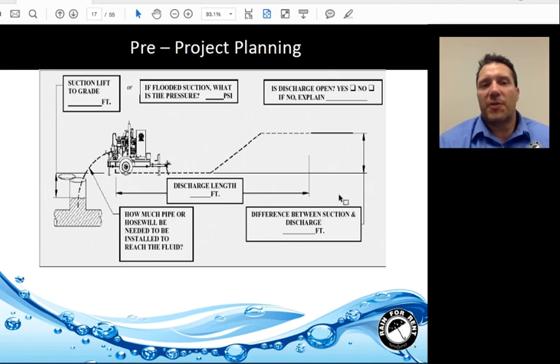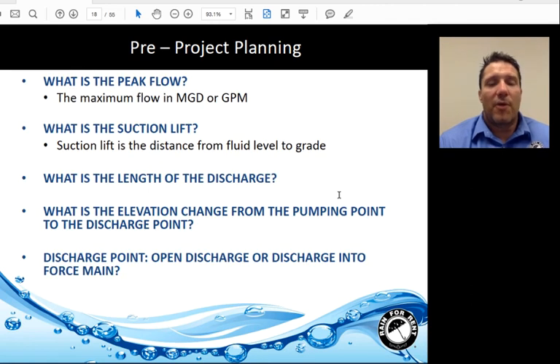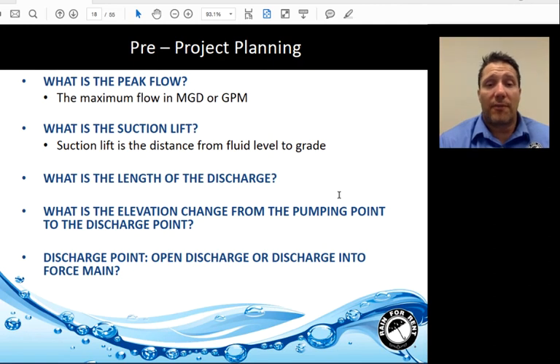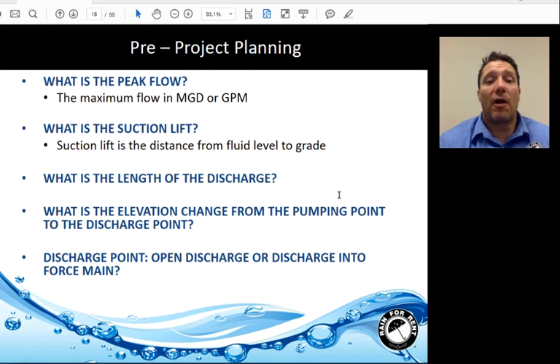This diagram is a good place to record information about the project site. The most important item is peak flow, followed by suction lift and fluid level to grade. The other items — length of discharge, elevation distance between pumping point and discharge point, and what needs to happen at the discharge point — are all items that, once known, will be used to design your system.